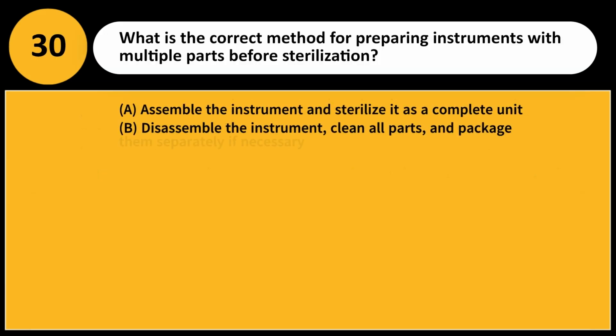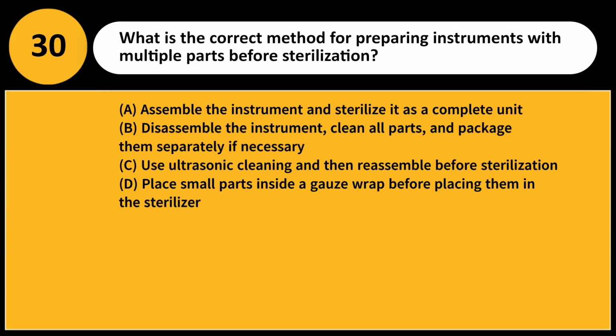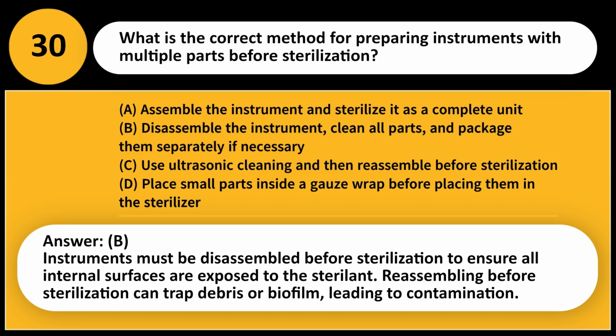What is the correct method for preparing instruments with multiple parts before sterilization? A. Assemble the instrument and sterilize it as a complete unit. B. Disassemble the instrument, clean all parts, and package them separately if necessary. C. Use ultrasonic cleaning and then reassemble before sterilization. D. Place small parts inside a gauze wrap before placing them in the sterilizer. Answer: B. Instruments must be disassembled before sterilization to ensure all internal surfaces are exposed to the sterilant. Reassembling before sterilization can trap debris or biofilm, leading to contamination.